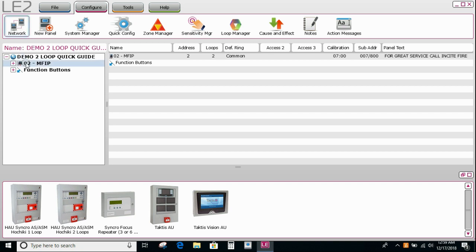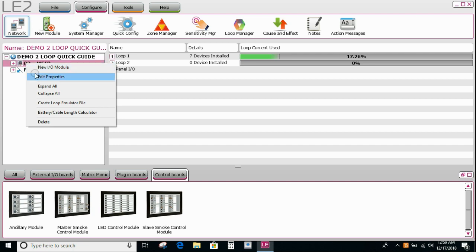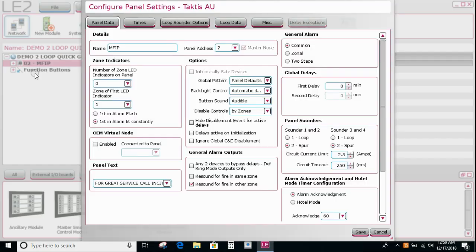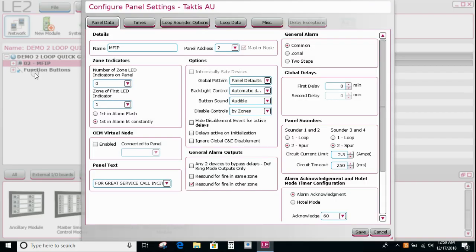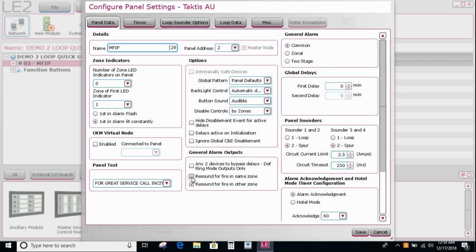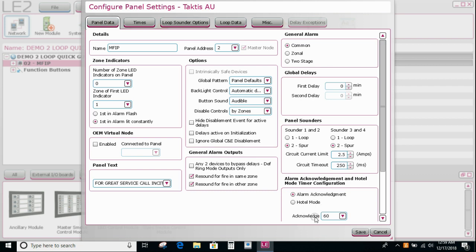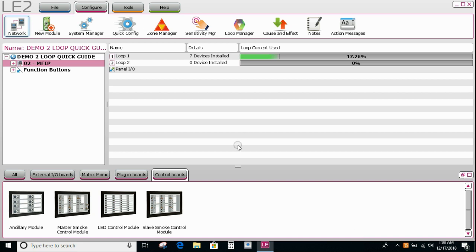So the next thing I might be doing if I was setting up a small panel is right clicking my panel and editing the panel details. So in here we can change the name as we did earlier, or change the panel text. We can also ensure that the resound for fire in the same zone is done. Certainly in the Australian market we always have that checked. We can set up our sounder circuits. There's four on Taktis: one, two, three and four. We can set them up as spurs or two loops, which effectively will then have some redundancy. This is where we can set the hotel mode or the alarm acknowledgement feature of the panel. And I'm going to save these settings as they currently are.